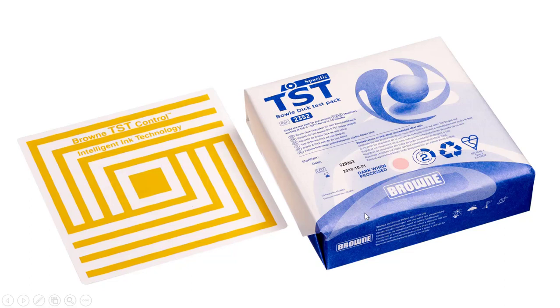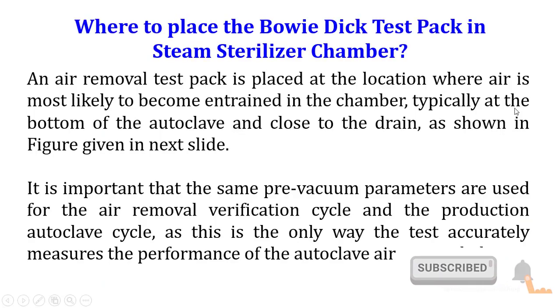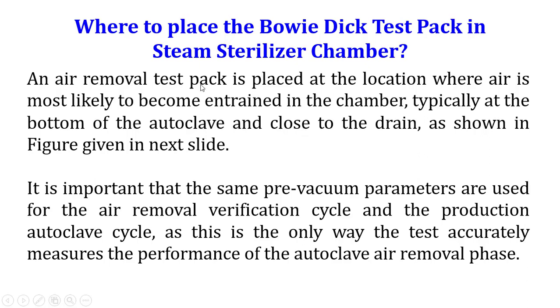The Bowie-Dick test pack is placed in the steam sterilizer chamber at a specific location. The air removal test pack is placed at the location where air is most likely to become entrained in the chamber — typically at the bottom of the autoclave and close to the drain, as shown in the figure in the next slide.